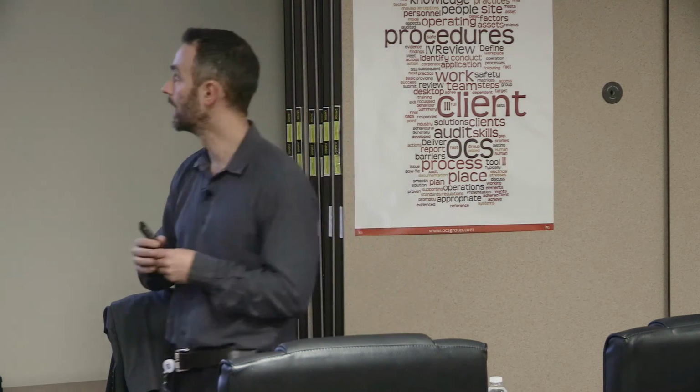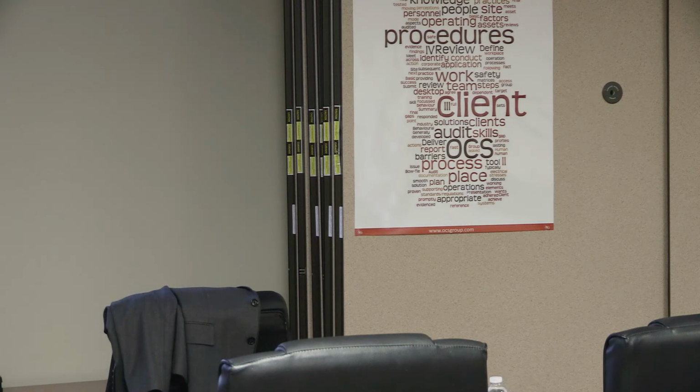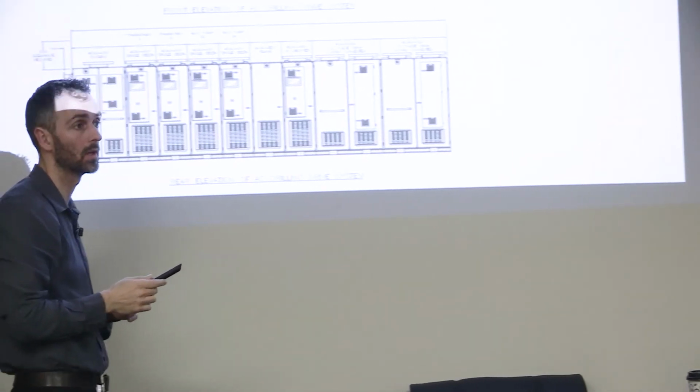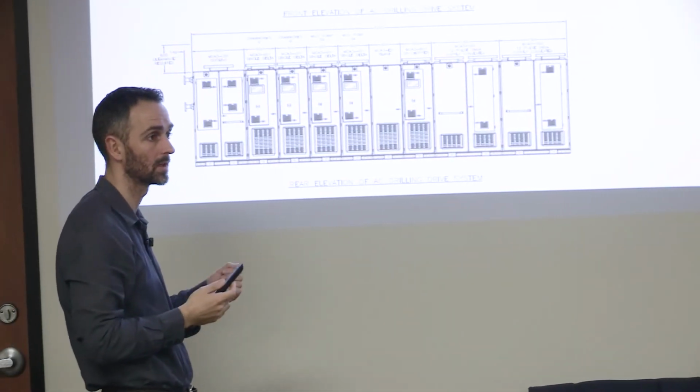One of the major things is, again, this battle for footprint, to be able to get the smallest and lightest boards out there. That presents this challenge, and what you end up doing is putting all of your controllers, all of your indication, all of your instrumentation in the same place that you have this enormous amount of power. And so that's a real focus for us to try to stop that happening. So what we do is we have main power sections that you have no access to. So these incomers, you can't get into them without shutting it all down or using a key system and getting in.